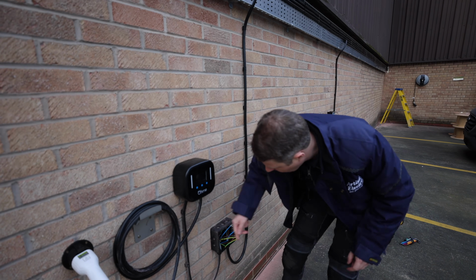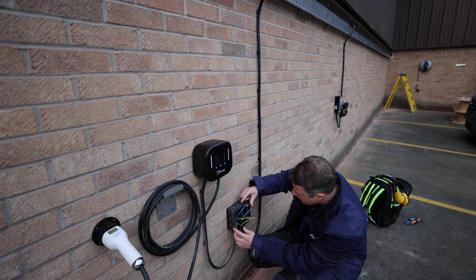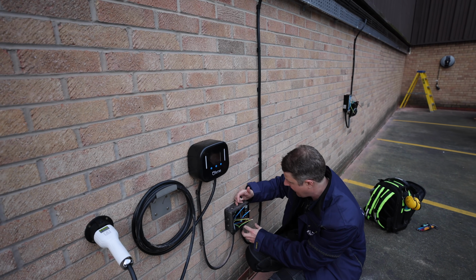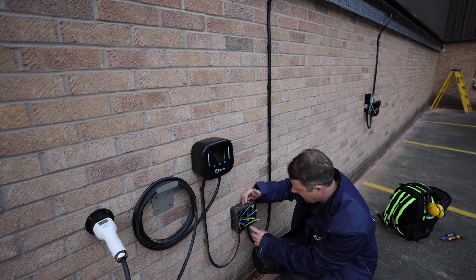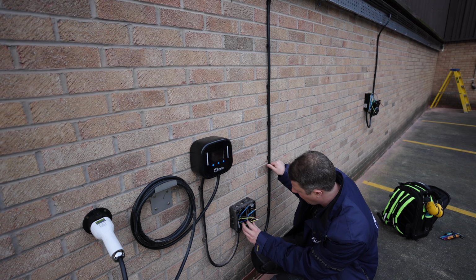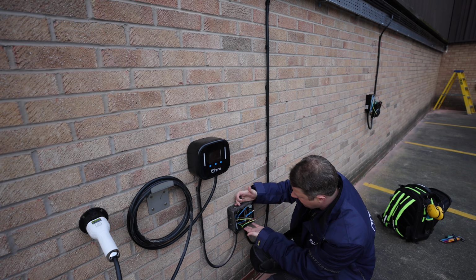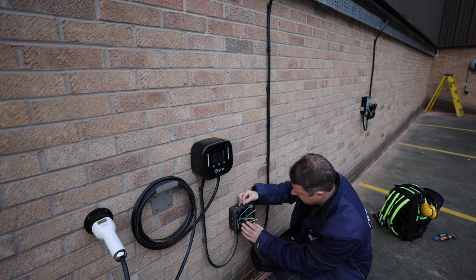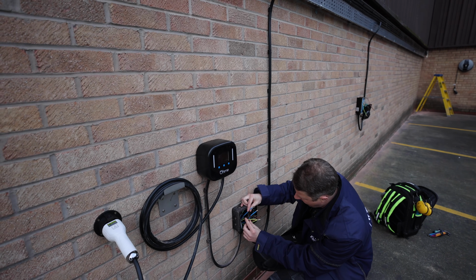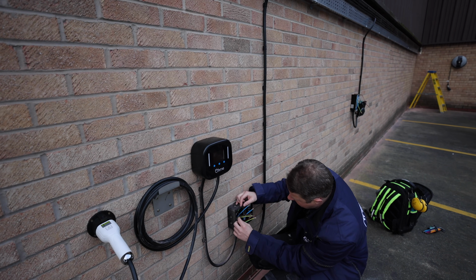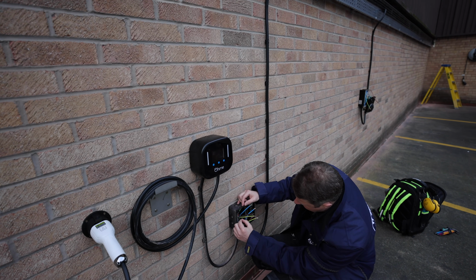It's just got this cable coming out of it, and then you've got to use a junction box like this to actually connect the cables together. So this is our supply cable, and we've used this Wiska box to connect our supply cable to their power cable, and the CTs are done in here as well.